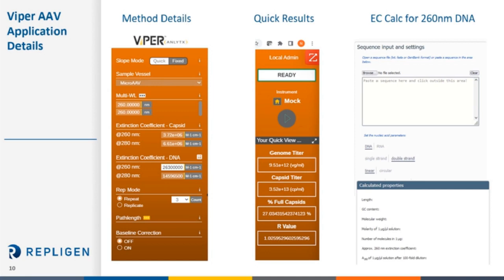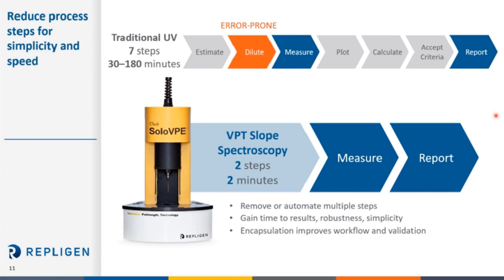The middle graph represents the genome titer concentration, capsid concentration, percent full, and the R value — the ratio of these wavelengths — which effectively becomes your OD value for which all the math is calculated. We also have a sequence input tool for determining extinction coefficients using a DNA sequence, integrated directly into the software to make method development easier. To summarize, we've taken traditional UV from a seven-step operation down to a two-step operation of measure and report, removing or automating multiple steps to gain time to results, ensure robustness and simplicity, and improve workflow and ease of validation for slope spectroscopy methods.